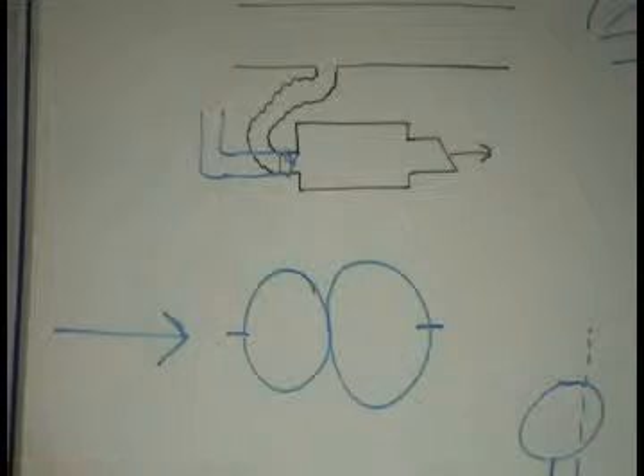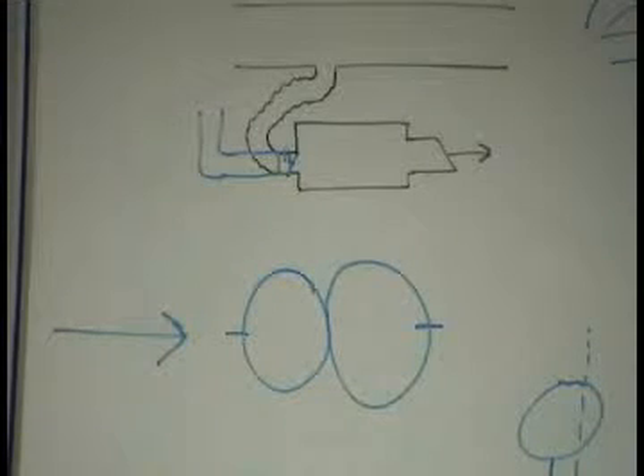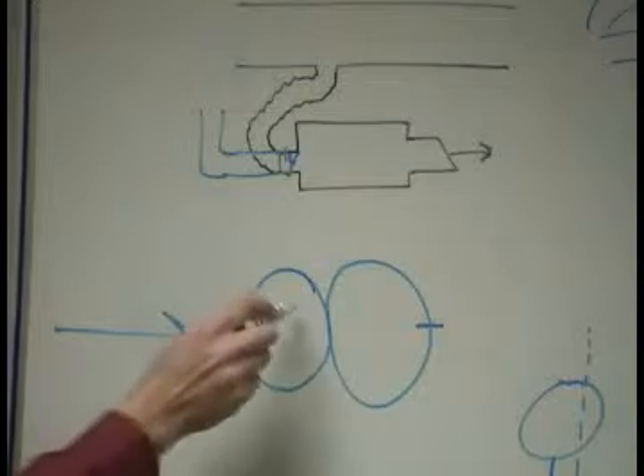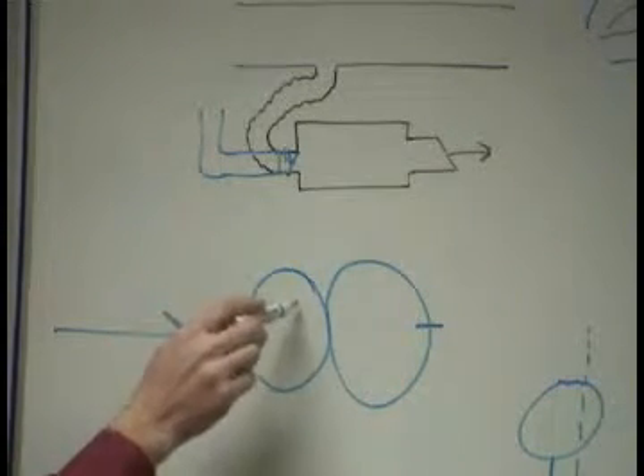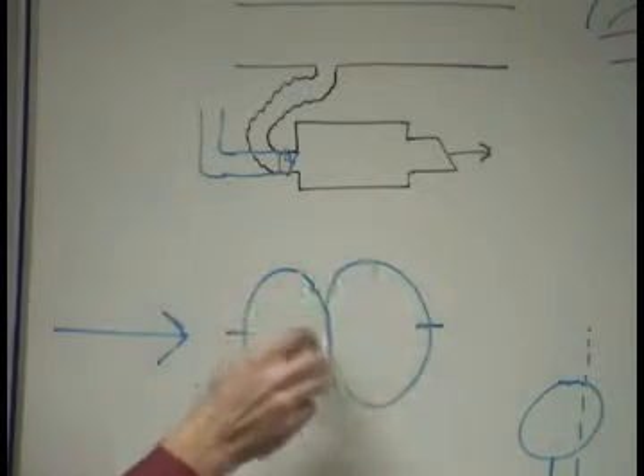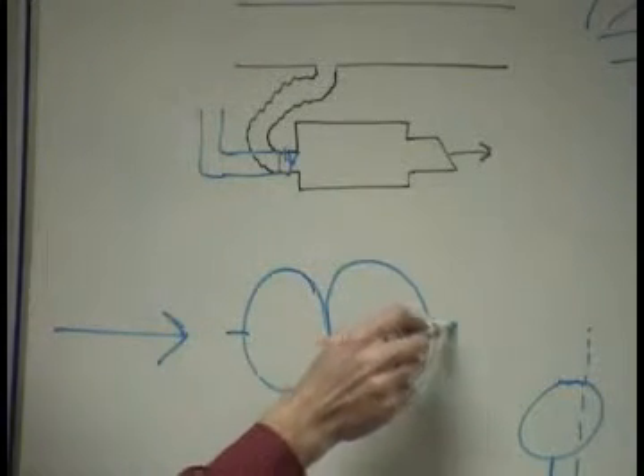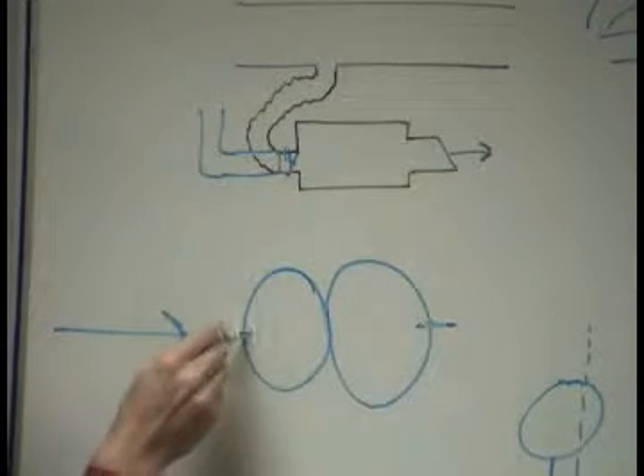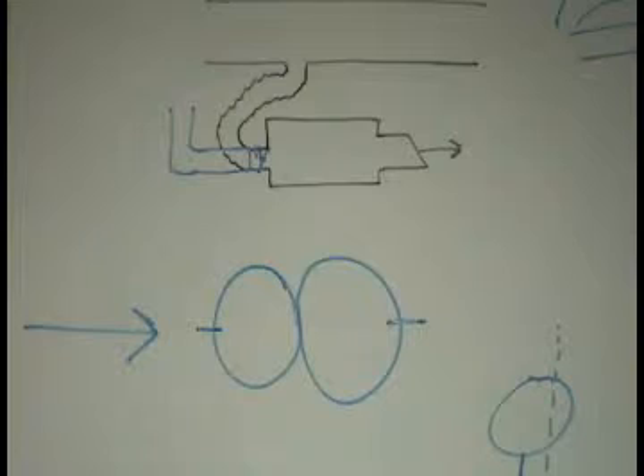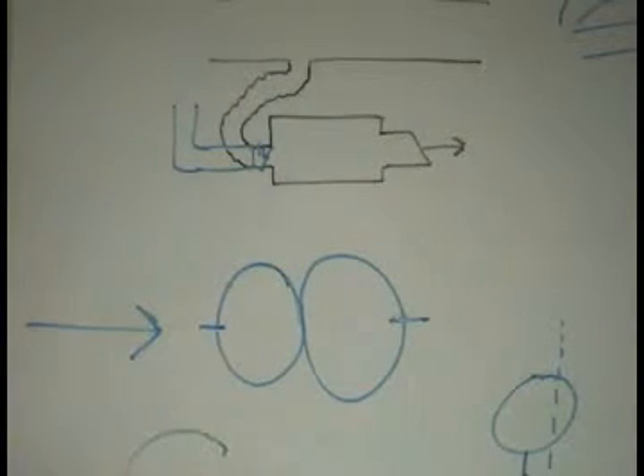Now, the box manufacturers will tell you that we don't use a pitot tube. We use a special amplifying, insert your trade name here. But when you open it up and look at it, all you see is this plastic thing. If I'm looking at a cross section here, here's one tube and here's another tube. They're back to back. One of them has holes on one side going downstream. The other one has holes going upstream. So if I'm looking down the duct, you got this thing here and there's a bunch of holes along there. And along the back side, you have the exact same thing.